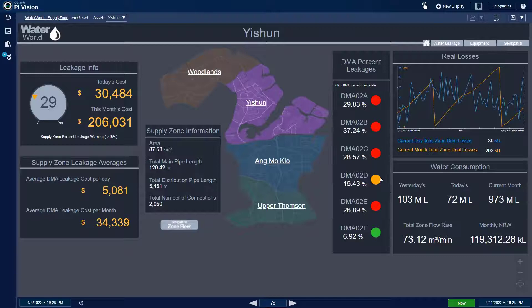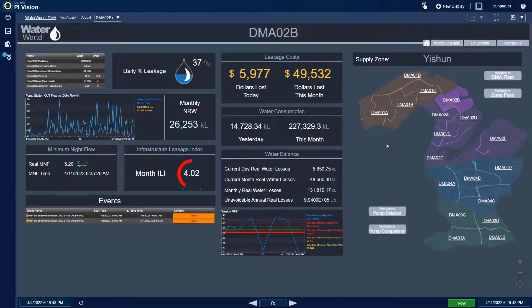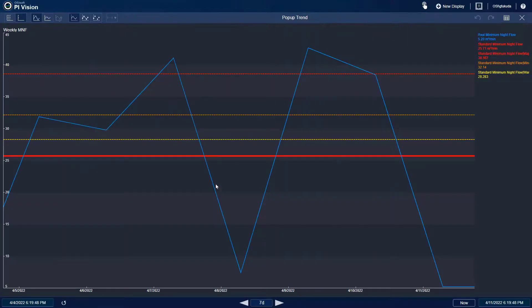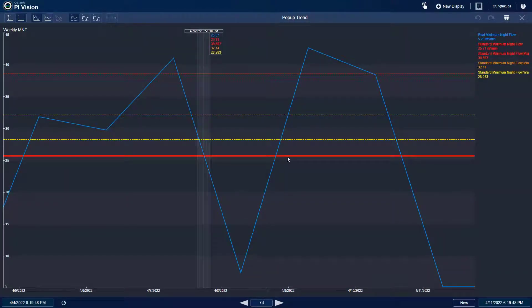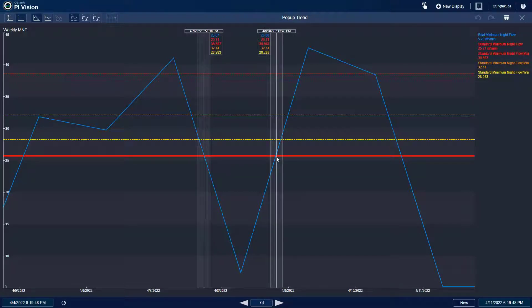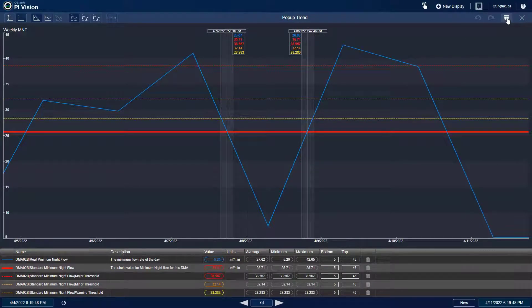The engineer drills down to the supply zone detailed dashboard, which shows consumption information, daily leakage percent, and daily and monthly cost associations. They also see a breakdown of all DMA (district metered area) percent leakages, noticing that DMA02B shows the highest percent leakage at 37%. Moving beyond the high-level overview, the engineer checks the NRW (non-revenue water) primary daily leakage KPIs, the monthly ILI (infrastructure leakage index) calculation, and the MNF (minimum night flow) trend. The MNF has exceeded the major alert level on two of the past seven days.